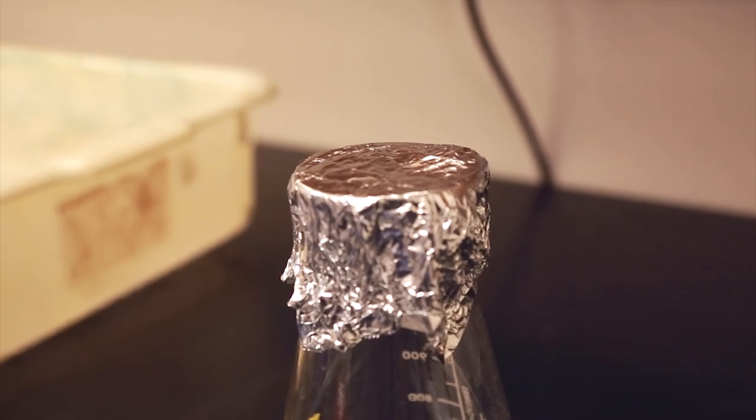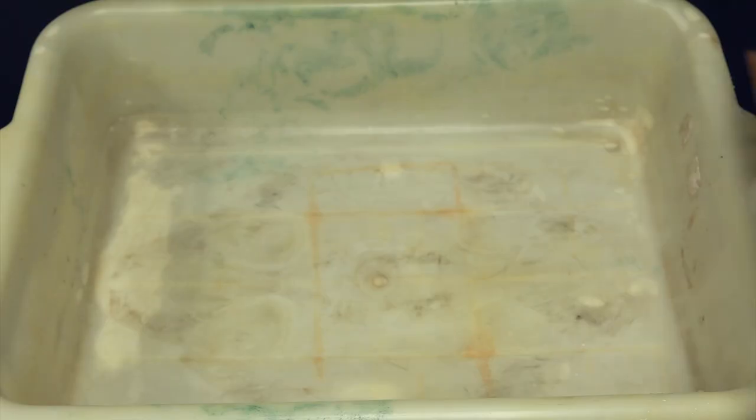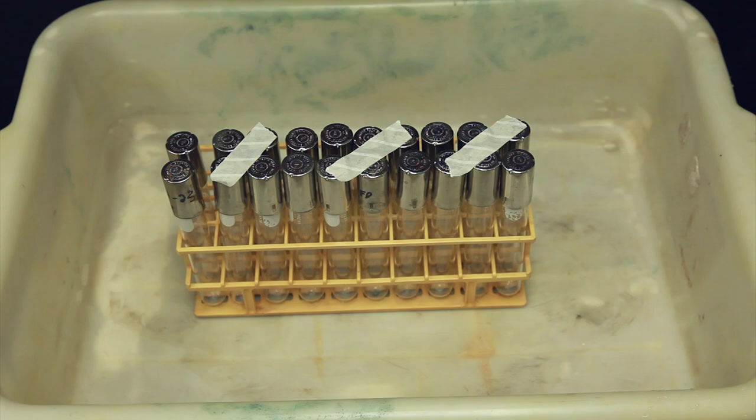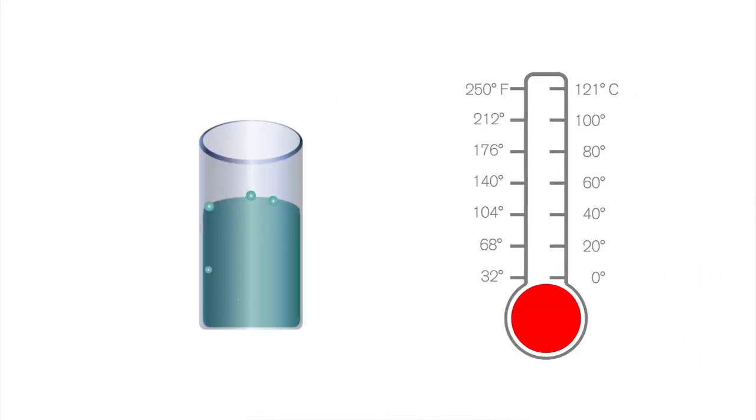Or, if the bottle has a screw cap, place the cap on so that it is still loose. About a half turn is enough. However, use care when loading glassware into racks and make sure there is space between items so that steam can move along pieces and effectively sterilize items. If you have glassware containing liquids, always use a pan to catch any liquid that may boil over.